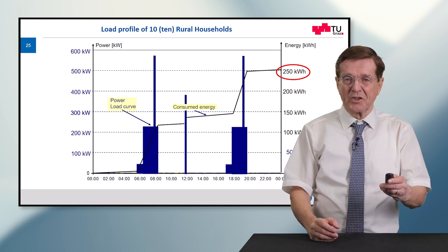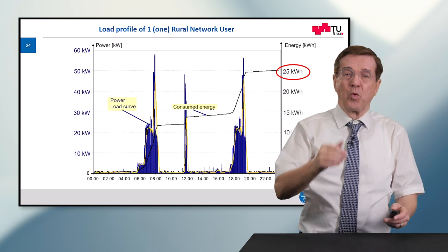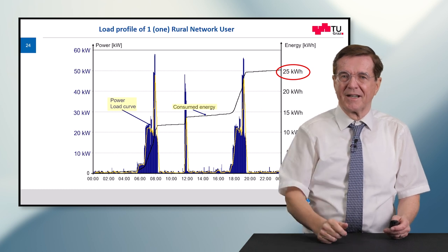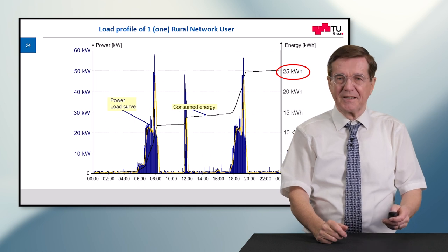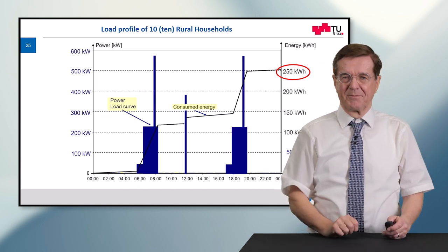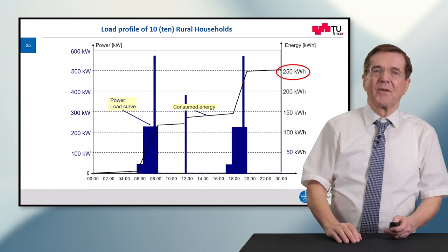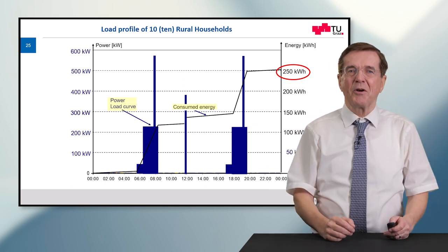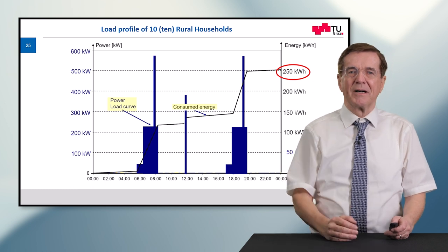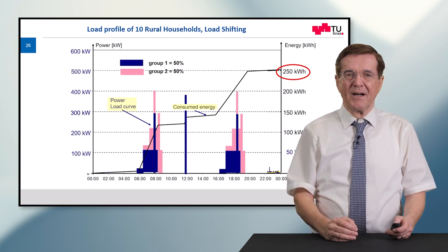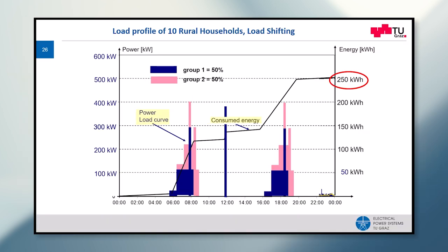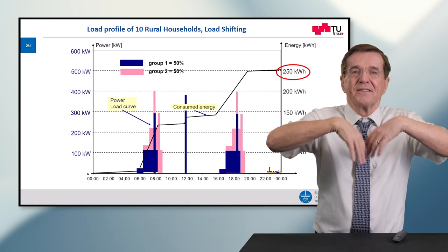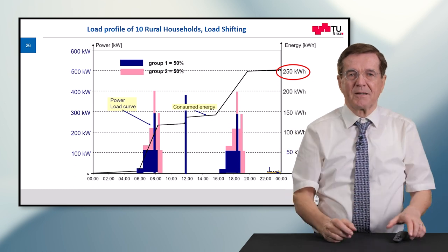Looking at the previous slide, one household has a peak of about 50 kilowatts corresponding to 25 kilowatt-hours, and if we have 10 households it's 10 times as much. If we have a problem with the cable cross-section and peak power, we can split the 10 households: group one is 50 percent and group two is 50 percent — each one has only half the peak load. By spreading these groups, the total peak load comes down.